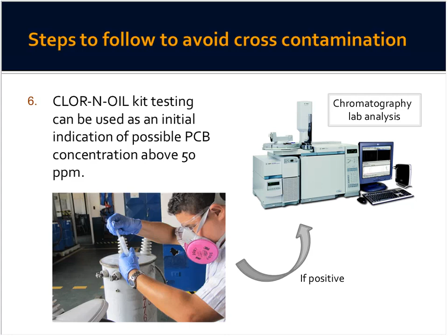Those equipment that have been passed through the screening with the CLOR-N-OIL kit and have proven to be positive and are pending chromatographic laboratory testing should be isolated also, because these are still potentially contaminated. They may not be contaminated, but they most likely will be contaminated. And here we have a label, a sign for the area that says pending chromatographic, which means they were pending to be sent to a lab. Equipment used that has come in contact with contaminated oil must also be labeled accordingly and stored separately.